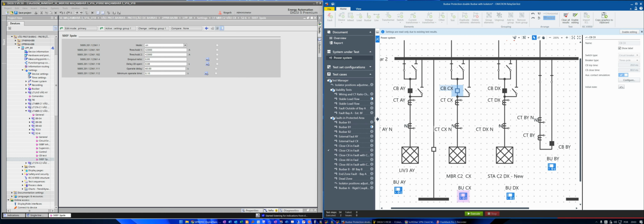So what will happen here? I have a current that you see in this CT, and my bus bar protection will put this current in the sum of the differential protection. And my bus bar protection will operate, even though this circuit breaker was open, and we clear the fault with the switch onto fault, for example, that operated in the remote terminal.